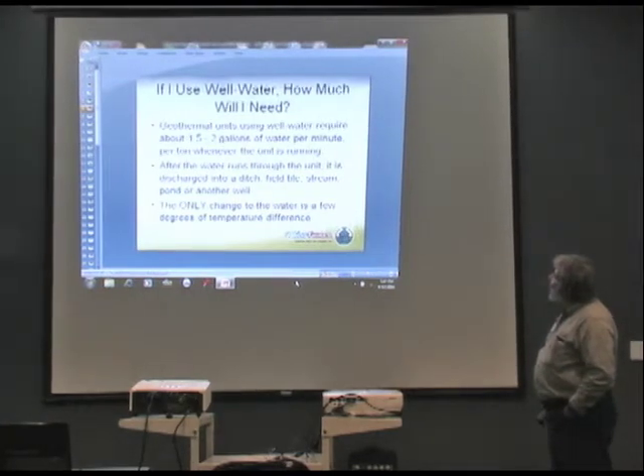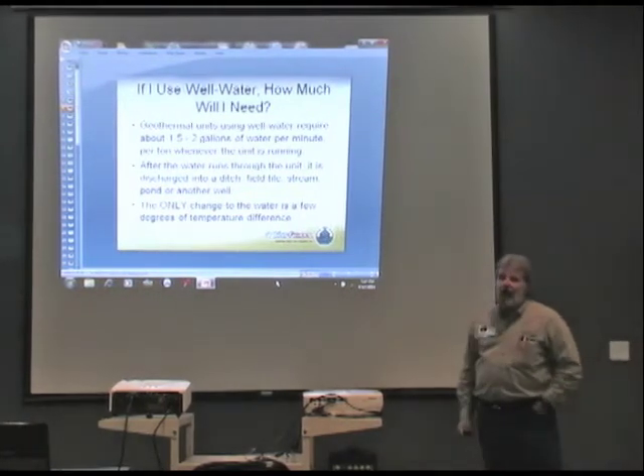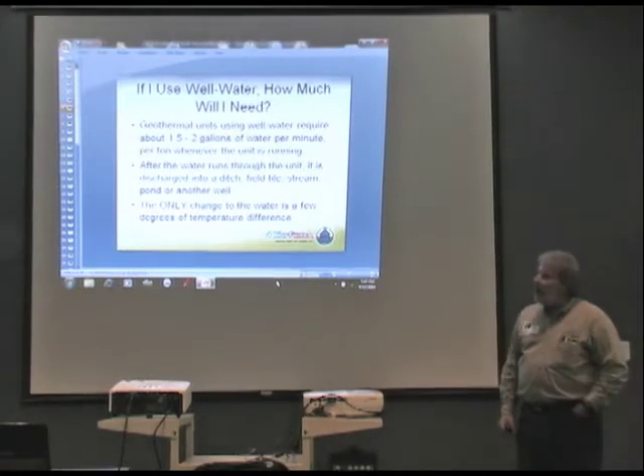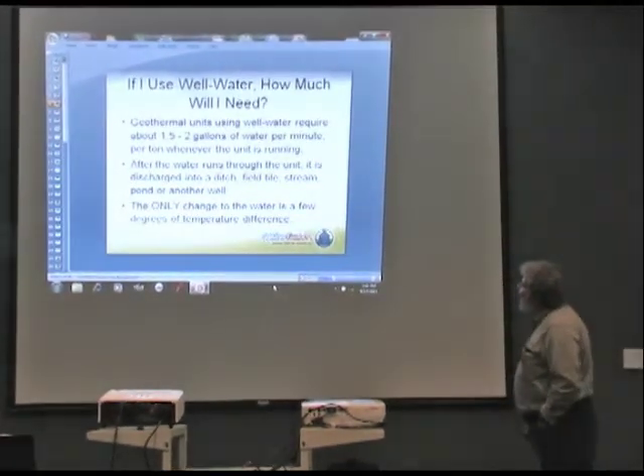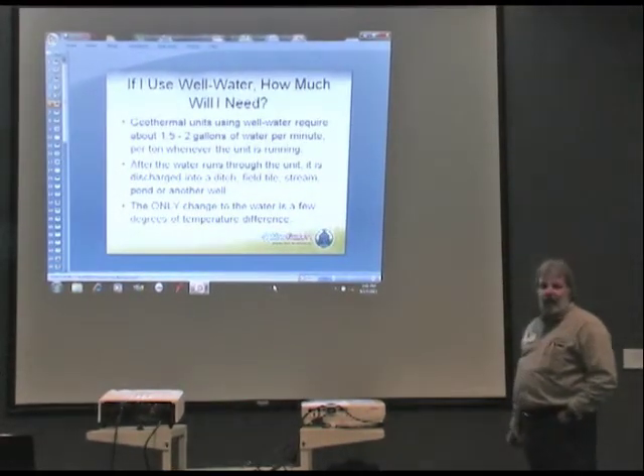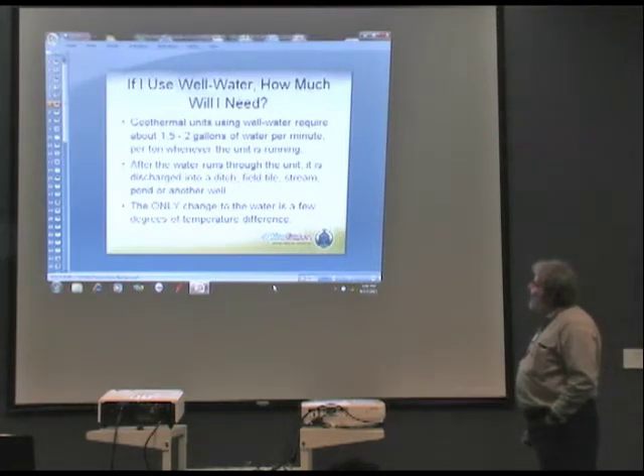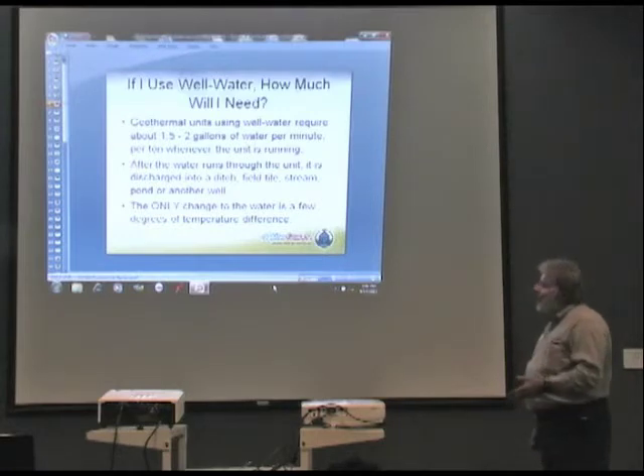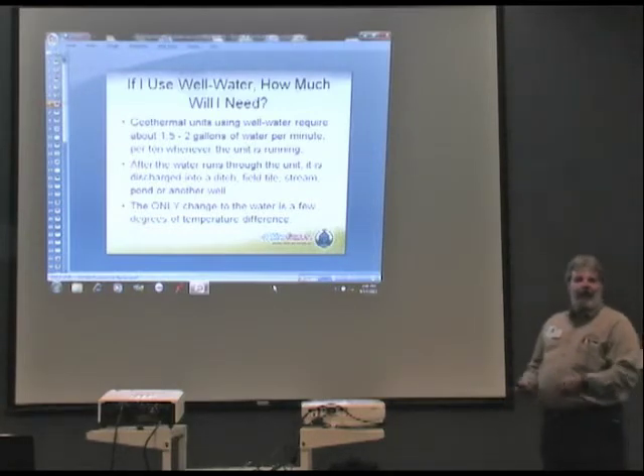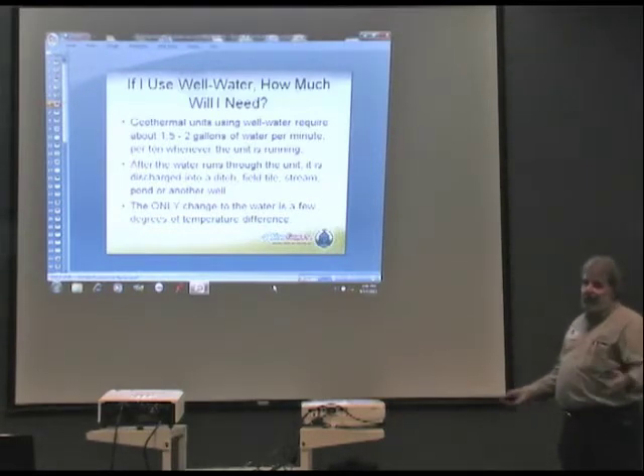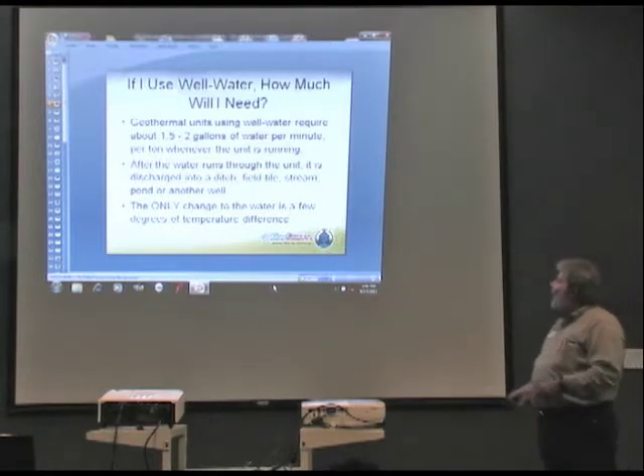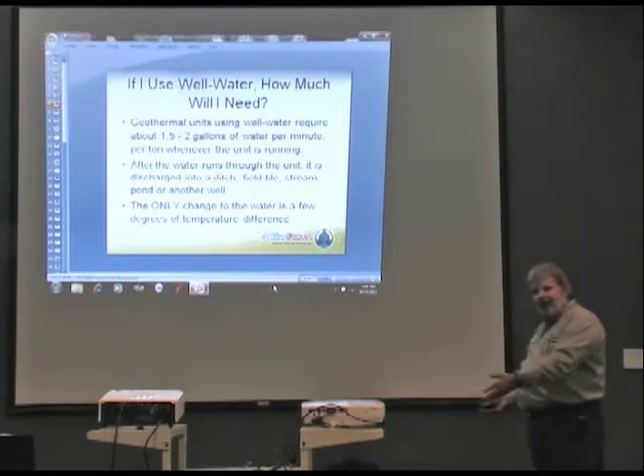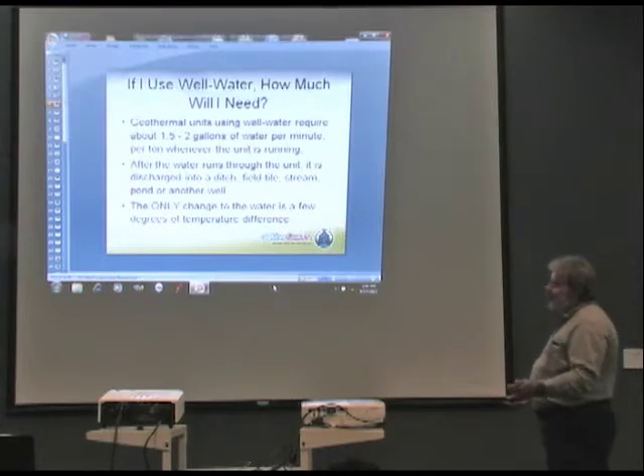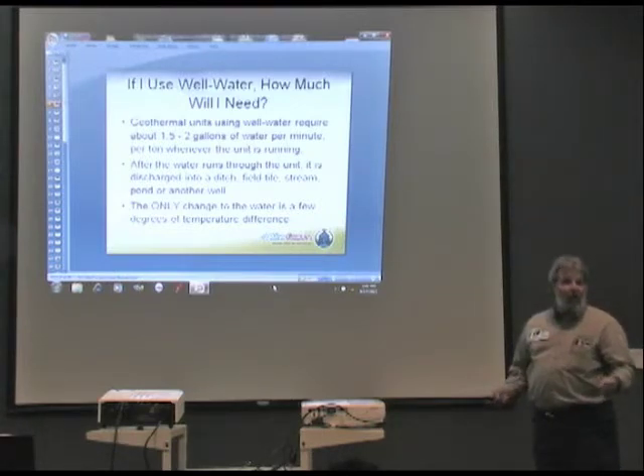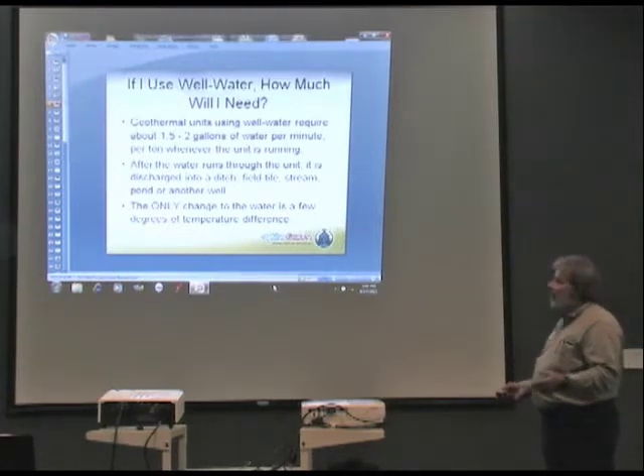If you're going to use an open loop and use your well water, you'll need a minimum of 1.5 to 2 gallons of water a minute per ton when the unit is running. After the water runs through the unit, it's discharged. We need either a ditch, or you can put a pond on your property, or we'll run it down a hill into the woods — but not onto your neighbors — because you're going to run millions of gallons of water through the system over the course of a year.